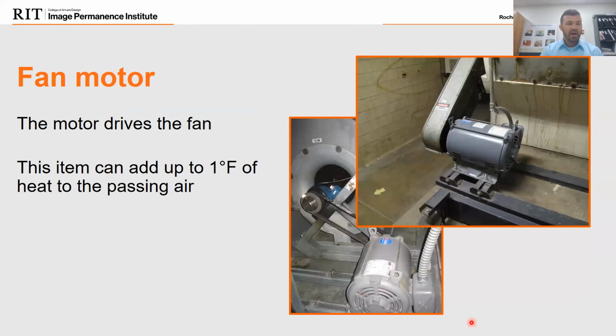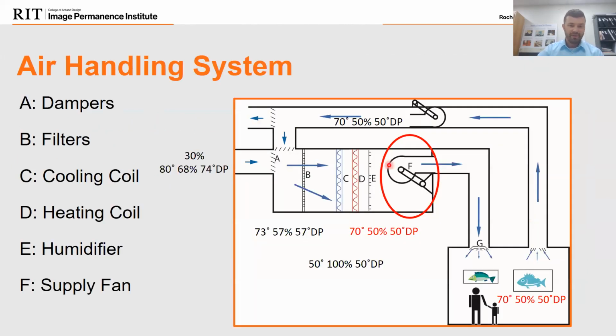Fan motor as well. The fan motor is what drives your fan. In some circumstances, the fan motor can add a degree of heat to the passing air. Again, I gave the process where everything's operating 100%, a perfect world scenario, nothing is malfunctioning. So we left our 70 degrees here and we don't pick up any heat. So in this scenario, we left our 70 degrees, we returned this air, exhausted some, brought in some outside air as makeup air, mixed it here. We had our condition, cooled the air, heated it, and got past our humidifier with no work, and supplied that air to the space. So in a perfect scenario, this is how the components would operate together to provide this condition.